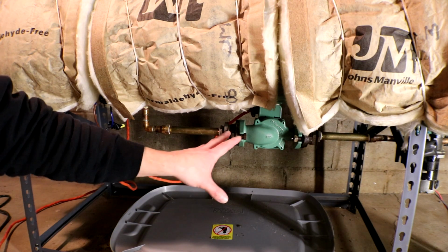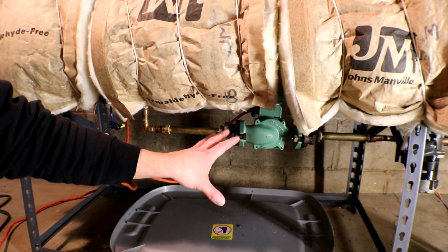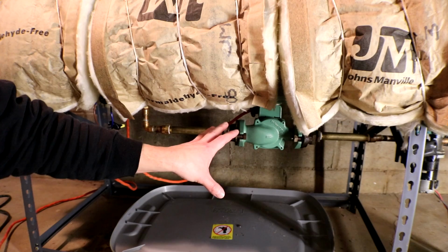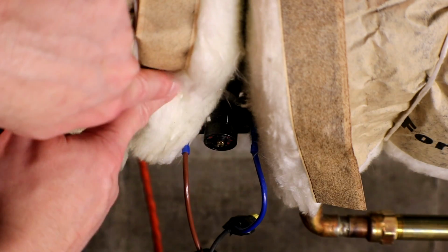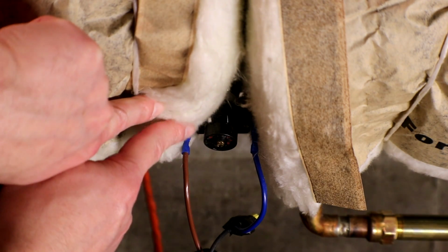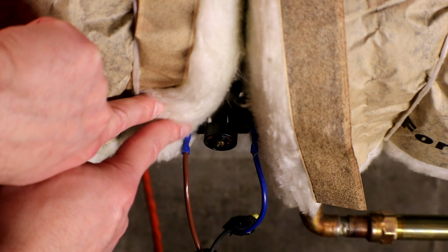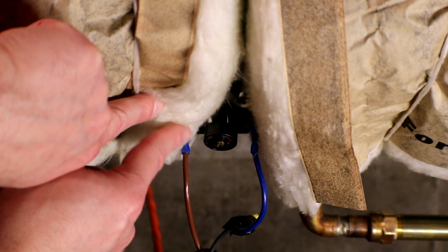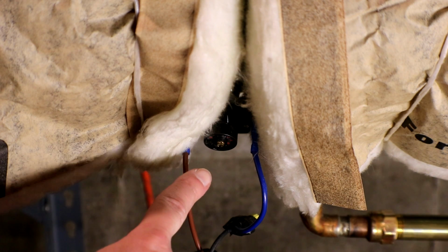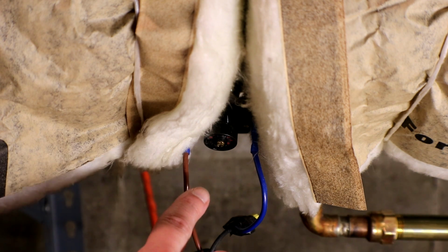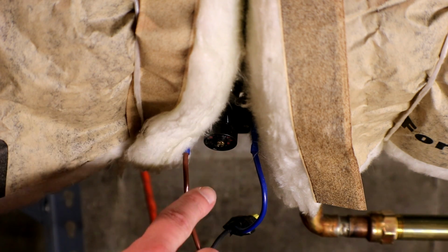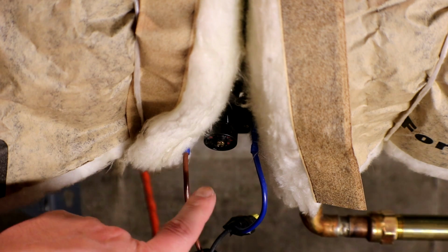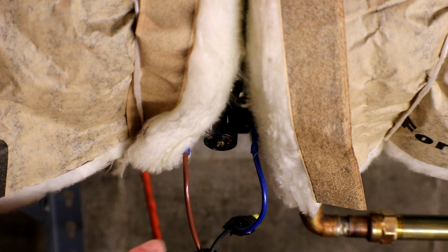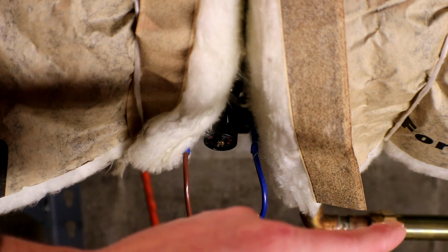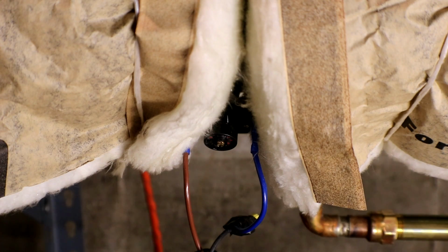Basically how this one works is based off a snap switch right over here. This snap switch is technically from a fireplace, like those blowers you can put inside a fireplace. You can adjust it from roughly 90 degrees Fahrenheit up to 130 degrees Fahrenheit, and I have it set to roughly 125 degrees. So once the tank heats up, it will close this circuit and turn on the lower Taco pump.